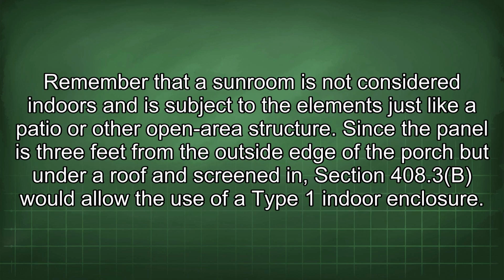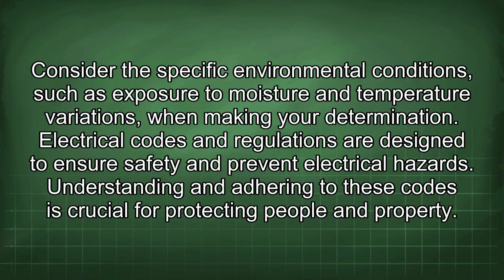Remember that a sunroom is not considered indoors and is subject to the elements just like a patio or other open area structure. Since the panel is 3 feet from the outside edge of the porch but under a roof and screened in, Section 408.3b would allow the use of a Type 1 indoor enclosure. Consider the specific environmental conditions, such as exposure to moisture and temperature variations, when making your determination.